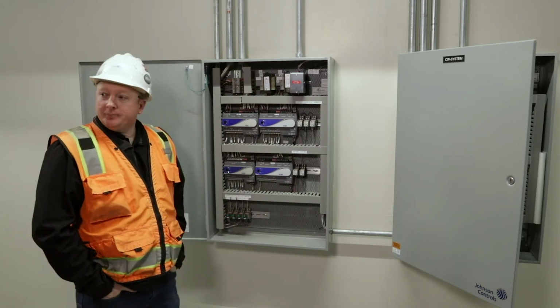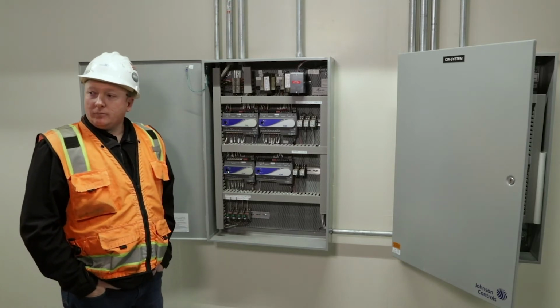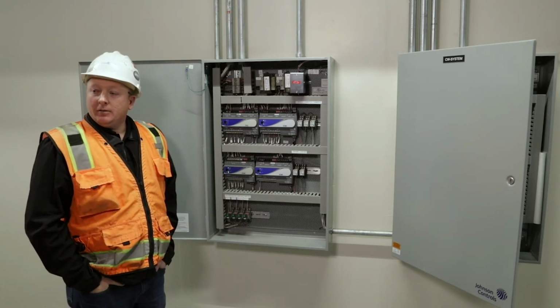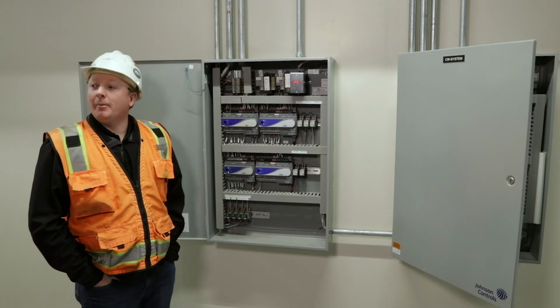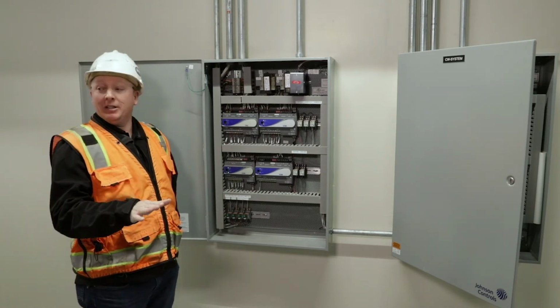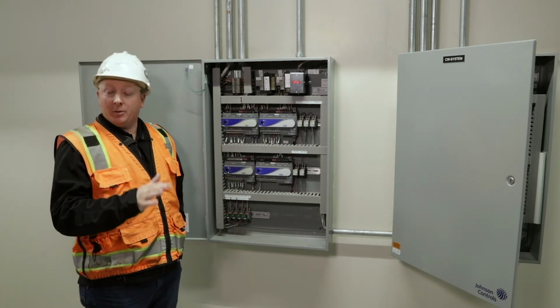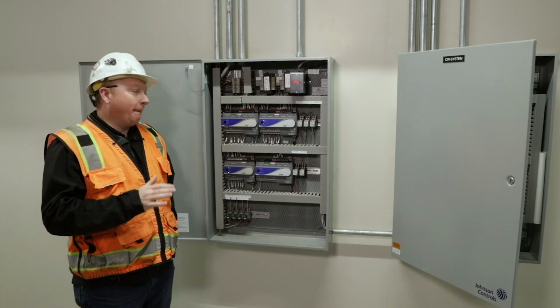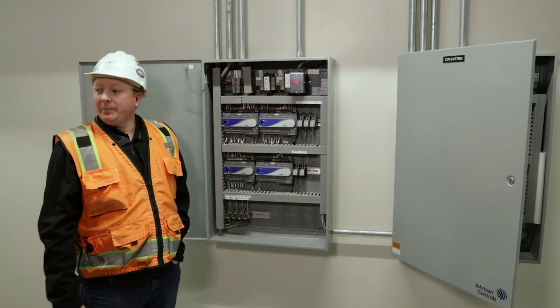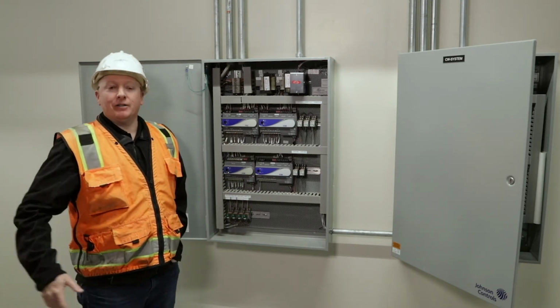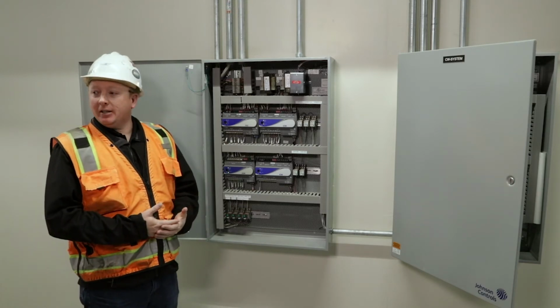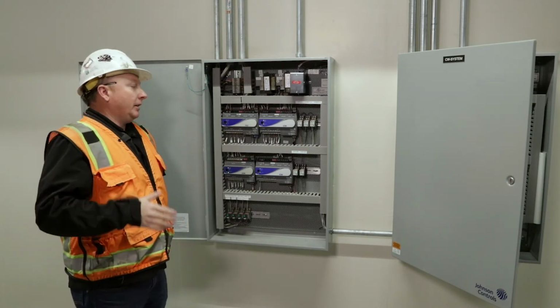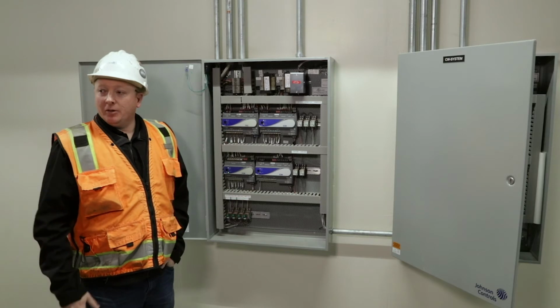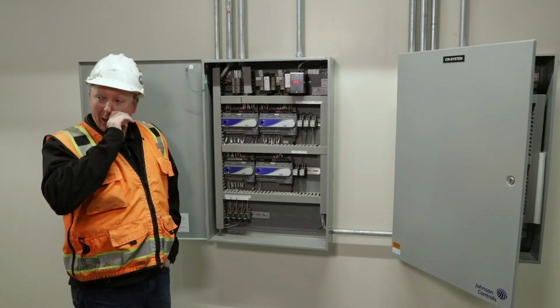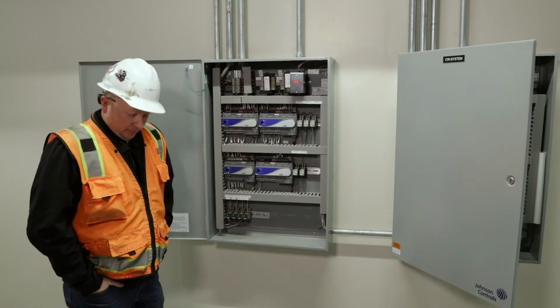So the secondaries don't have VFDs on them? Secondaries do have VFDs, just the primaries. Okay. So the only pumps in here that don't have VFDs are the 3 primary chill water pumps, and they don't have starters either. Constant flow. Yeah, those are just constant flow because we are on a primary secondary system. So the primary pumps are constant flow, and the secondaries are staged.